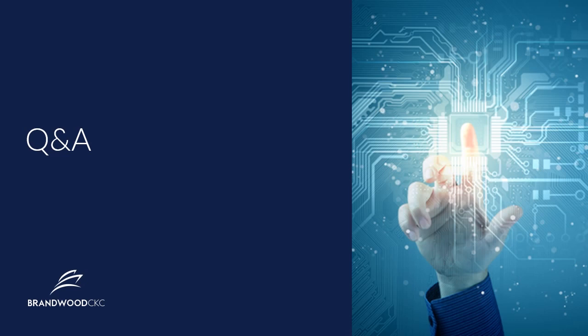The standards to be followed for analytical performance is per the IVDR. If a performance study is conducted as per ISO 20916, will it be accepted in the IVDR? Yes, effectively, there's no specific guidance that this ISO standard is required or not required. That ISO standard, which is 20916, is a very good indication and meets the general requirements for notified bodies that are reviewing under the IVDR.